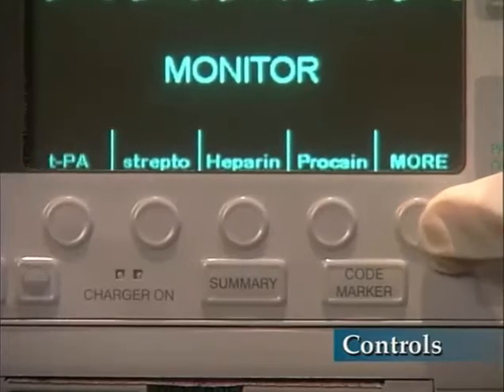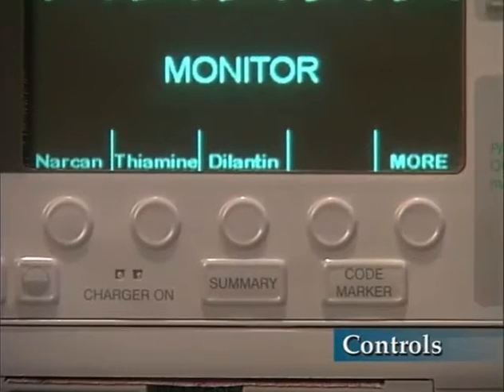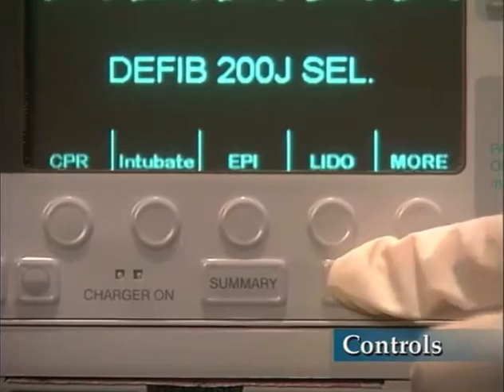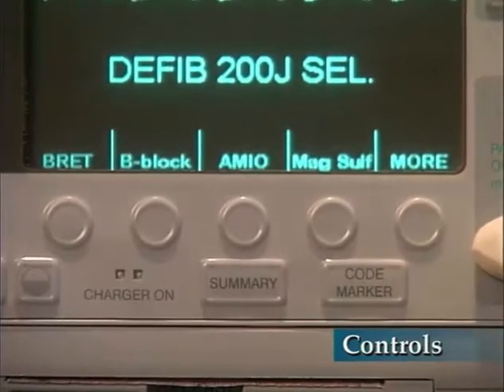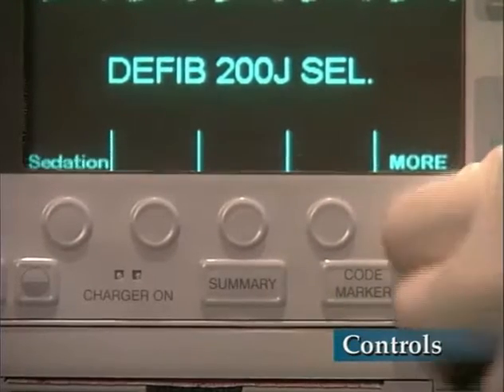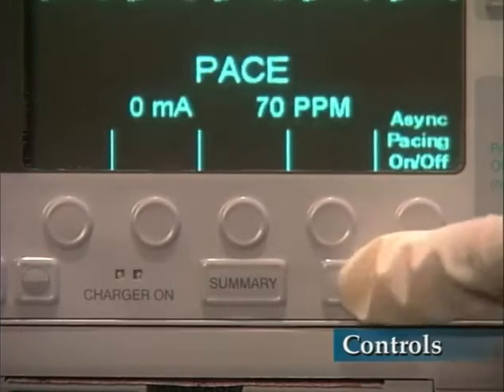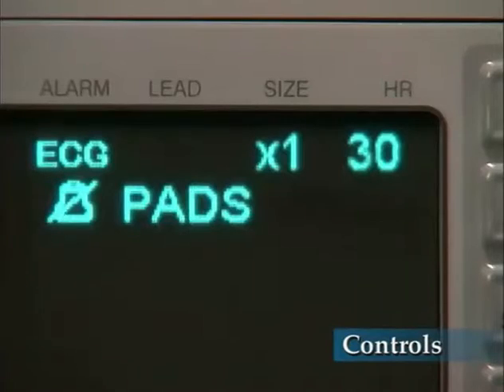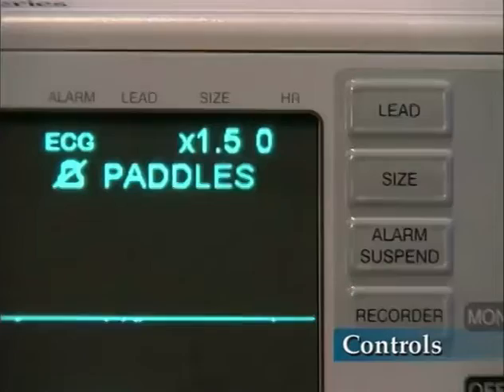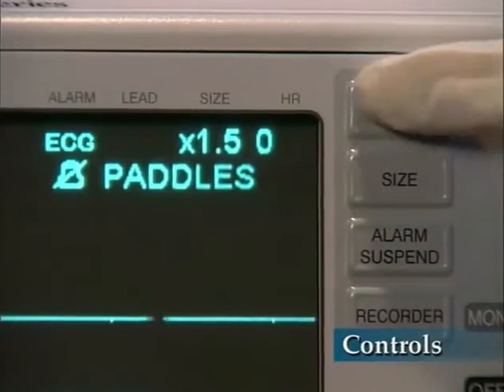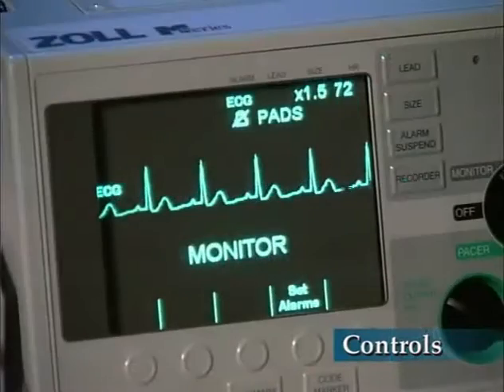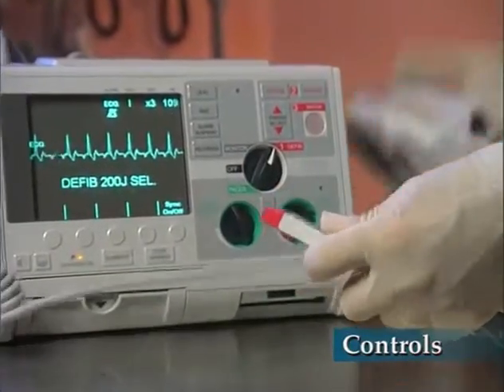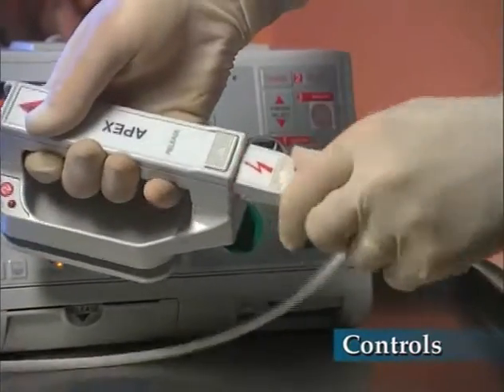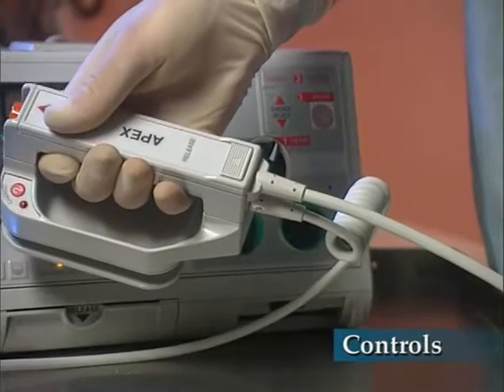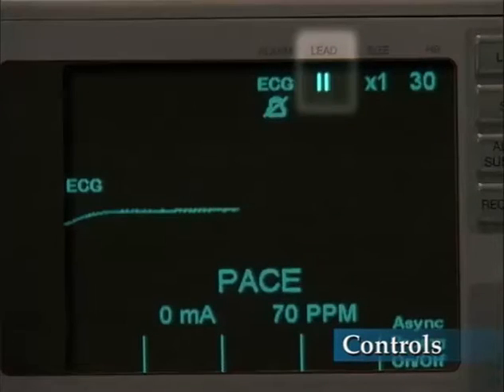The 5 soft keys are used for code marker and other functions depending on the operating mode of the device. Labels for the soft keys appear at the bottom of the display directly above each key to indicate its function when these features are used. The default lead setting, pads or paddles, is selected when the device is turned on in defib or monitor modes, and multifunction electrode pads or paddles are connected to the universal cable. Lead 2 is automatically selected when the unit is turned on in pacer mode.